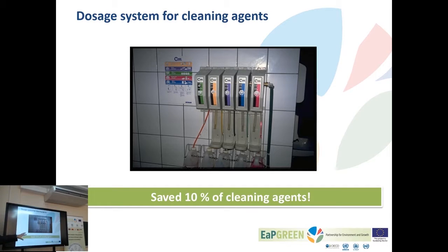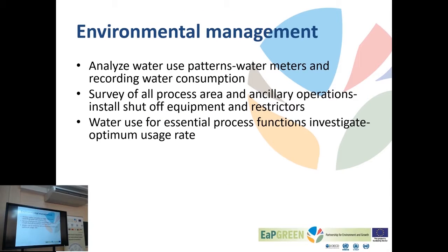Many major suppliers of chemicals have started to supply this dosification equipment at no or very low additional charge, to make sure you're using their chemicals properly. Because, as we'll discuss in a minute, some chemicals — if you put in more — don't work better, but worse. There are optimum concentrations for many chemicals. This information we need from the supplier, from the technical data sheets, which need to be processed and known to the operators.